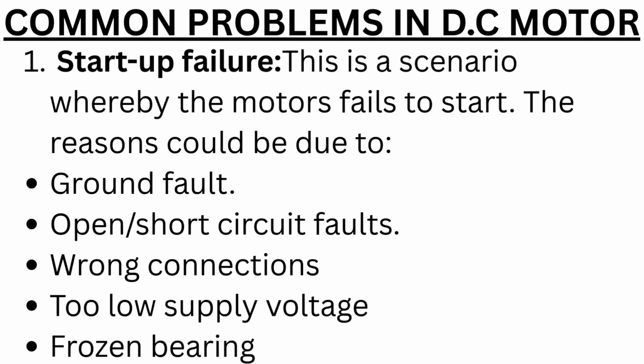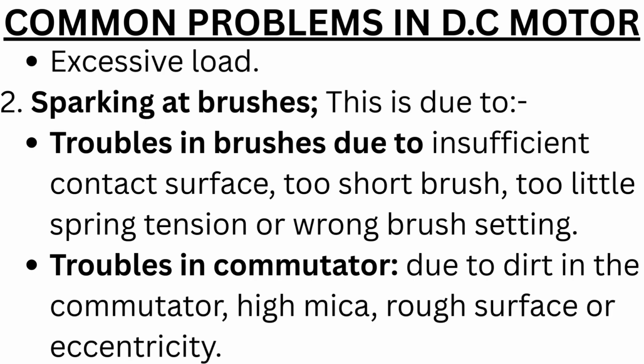They are 1. Startup failure. This is a scenario whereby the motor fails to start. The reasons could be due to ground fault, open or short circuit faults, wrong connections, too low supply voltage, frozen bearing, excessive load. 2. Sparking at brushes.